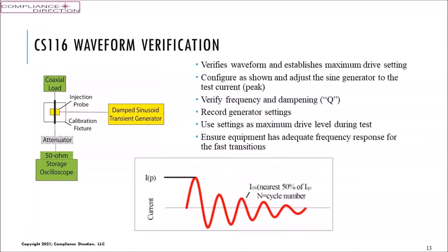CS116 is a similar kind of function here with a dampened sine generator. And we use a time domain oscilloscope. We verify the waveforms and adjust to the peak. By the way, go back to 115 for just a moment. The settings that we collect during that calibration of the waveform are used to drive the test. We're not using it as a maximum, we're actually setting. So the test could see more or less current than we got through our calibration. But the standard tells us to do it that way.